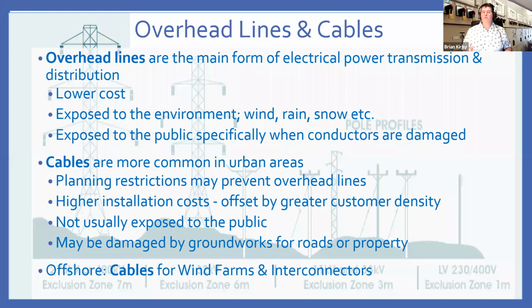So in urban areas where you don't have the capability of running overhead lines through towns and cities, cables are more common. There are more planning requirements for cables, and the cost of installation is higher, but the advantage is you're not usually exposed to the public. But you do have the risk that any groundworks going on, someone digging up the road to replace pipes or put in foundations for a new building, may accidentally damage them. Offshore, cables are almost exclusively used because it's just not practical to try and run overhead lines over the sea.